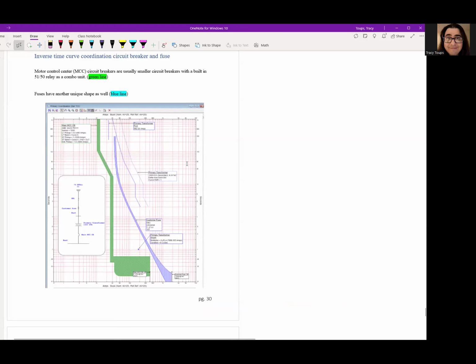So here's a good example. We have a green line, which is a downstream motor contact. Right here you have the motor itself, that is this big green line, which is typically a motor circuit breaker. A motor circuit breaker has both the protective function and the circuit breaker all smashed in one device, and this is typically the curve for that. You have the little blue solid curve. This is a custom fuse they put right here on the high side of the transformer. You see in this instance, it's a small transformer, so they could put a high side fuse here for protection.